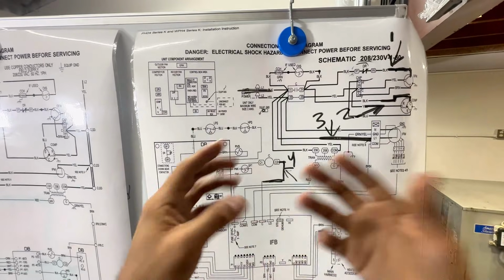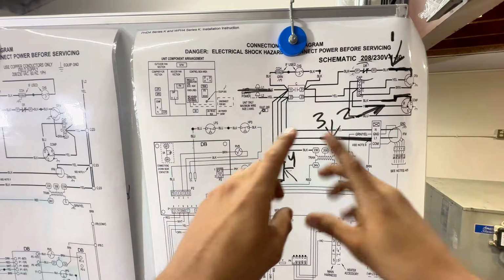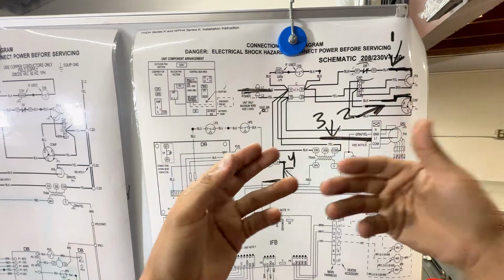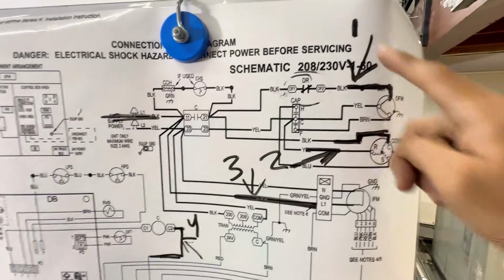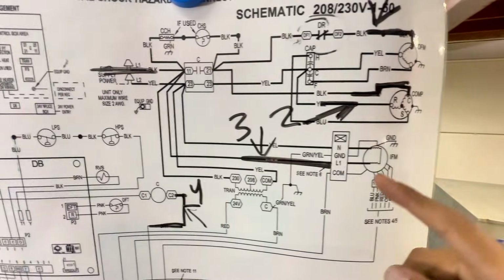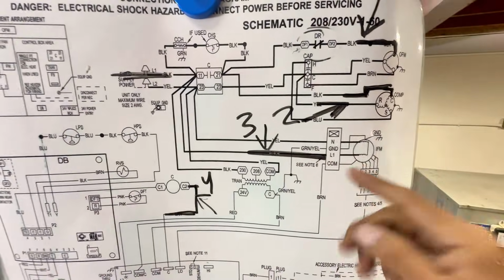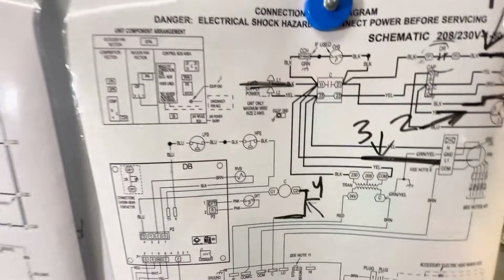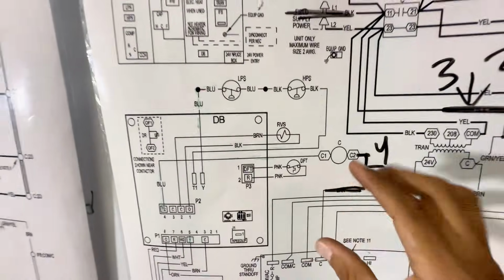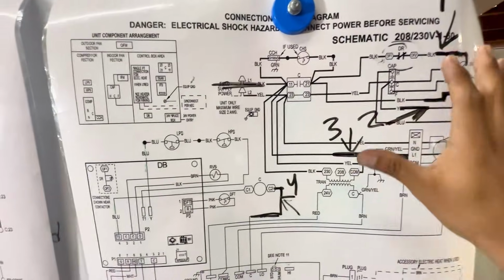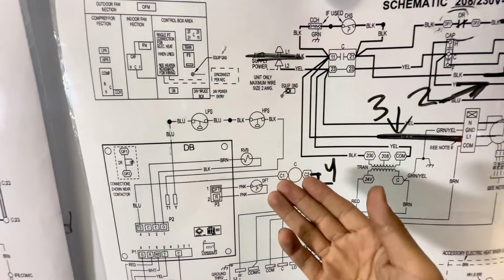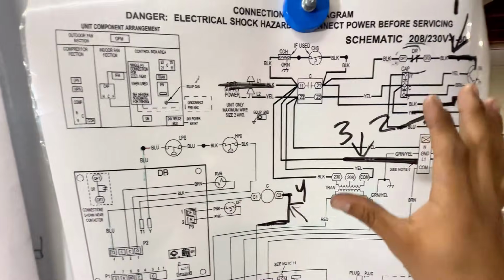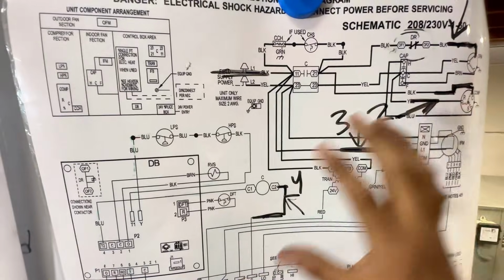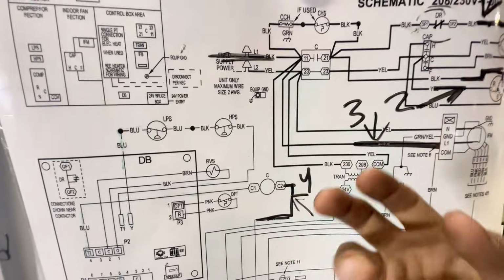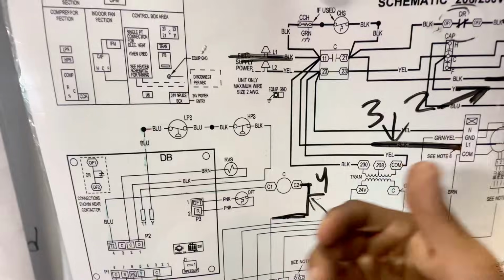All right, so before we go into the unit and check amp draw, I highlighted the areas where we're going to be checking for current. So we're going to be checking the outdoor fan motor, your compressor, the ECM indoor fan, your contactor coil. So you notice, right? These are high voltage components. This is a low voltage component or low voltage load. And these are high voltage loads. But you can still check amp draw regardless of the voltage, as long as it is a live circuit.